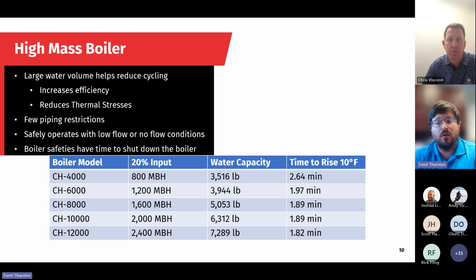What we want to avoid, and will happen, is tripping the high limit, which causes the boiler to cycle. Cycling is about a 2 to 5 minute process. It will happen where there's a post-purge where the blower motor blows air through the boiler and out the stack, has to wait for a new call for heat, and then goes into pre-purge where it again blows air through for safety reasons, so there's no combustibles in there. But this purge cycle has this cold, room temperature air pulling the heat out of the boiler. And so each time you cycle, you are sending heat and money out the stack.